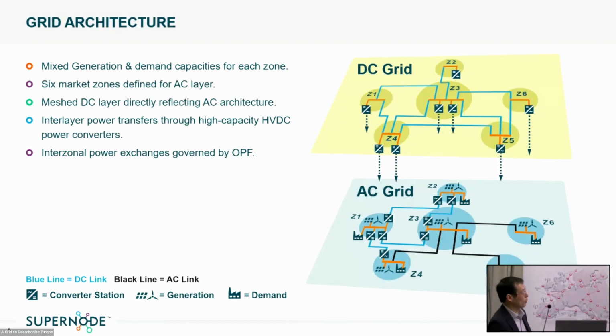The power flow between the DC and the AC is through the dedicated high capacity HVDC converters, and the set point and the power flow within the zone itself, and also between the AC and DC zones, are governed by the OPF results. We calculate the OPF results, then give certain set points for the different DC converters and for the different generations.